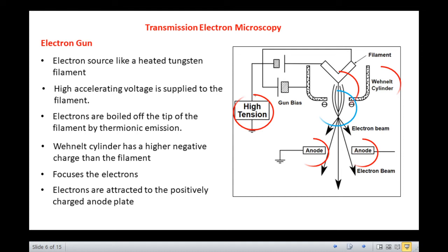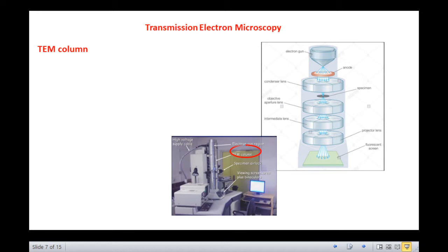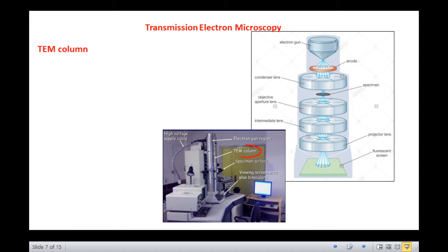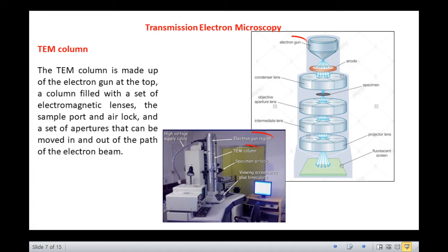Let us now talk about the TEM column. The TEM column stands vertically as you can see here and is made up of the electron gun at the top, a column filled with a set of electromagnetic lenses like the condenser lenses, objective lenses, and projector lenses, the specimen port and airlock, and a set of apertures that can be moved in and out of the path of the electron beam.